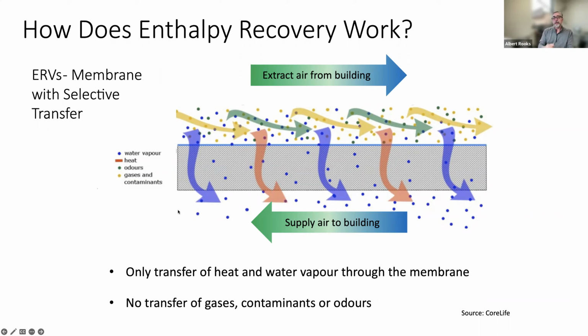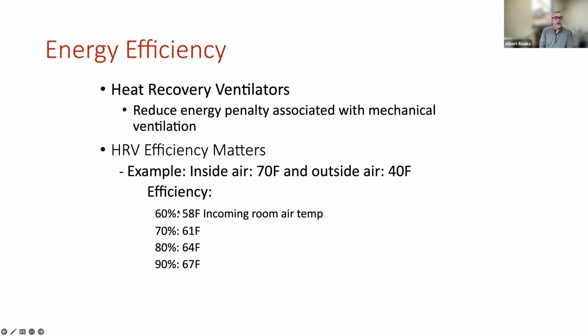And so the airflow that has no moisture just basically draws that moisture across the membrane and into the building. And that's really how we manage moisture through the ventilation rate. So we can actually set up a building, understand kind of what the conditions are, and then tune it based on the equipment that we're using and the flow rates that we use to manage the moisture and keep the building in a really nice comfort zone.